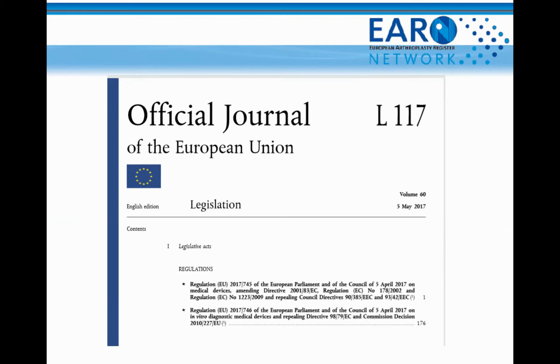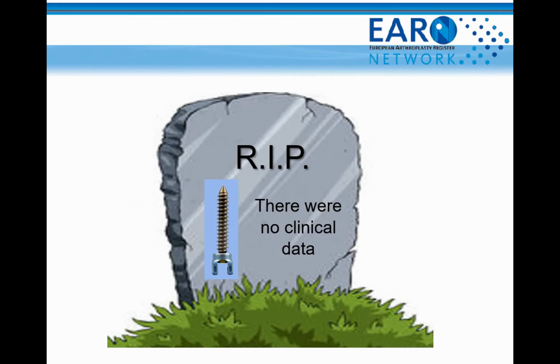Despite the recent delay of MDR implementation, it is highly recommended to prepare for that to avoid overload of resources and processes. Particularly collection and processing of clinical data, which require significant time for adaptation, are already addressed in MEDDEV 2.7/1 Revision 4 and applicable now. It is possible to implement core aspects of MDR even now and reduce the need for change when it comes to formal submission for MDR CE certificates.